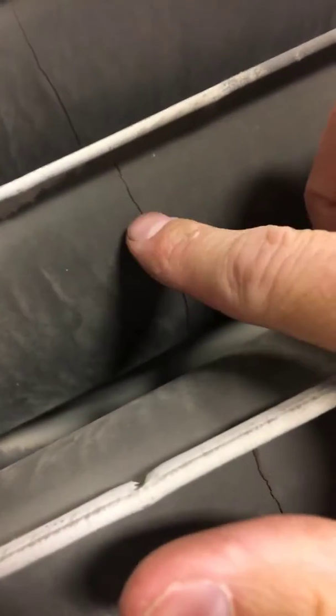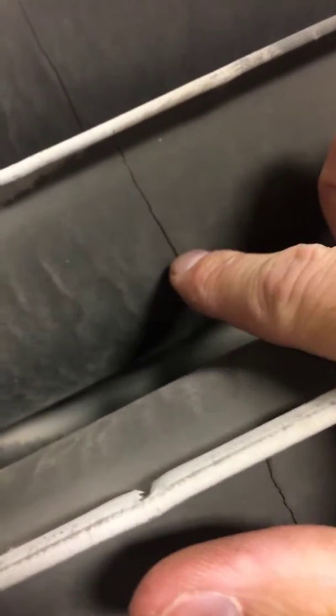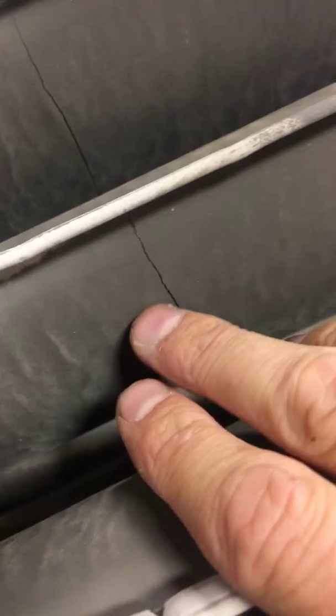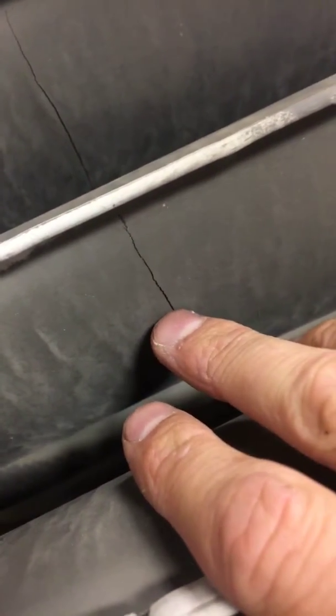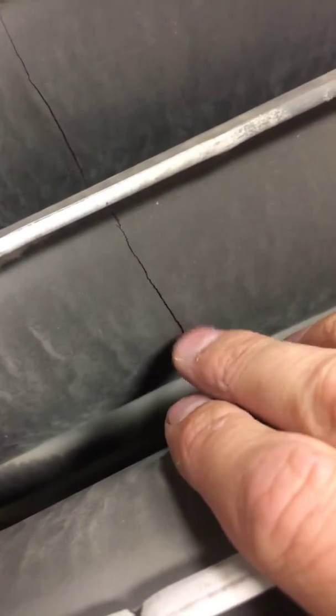These are pretty big cracks that come through here, so definitely watch out for those. This one in particular, in the middle, we found was leaking carbon monoxide. These two surprisingly were not, but this one here, I don't know if it was separating when it was heating up or what, but this was leaking carbon monoxide right out of it. Not very much, about 13 parts per million, but it does leak.